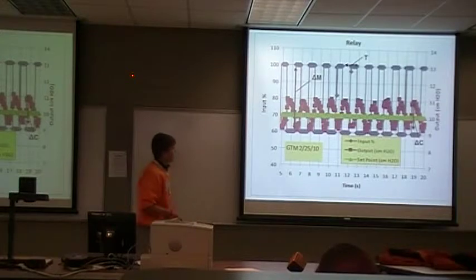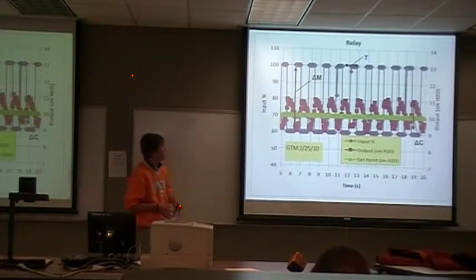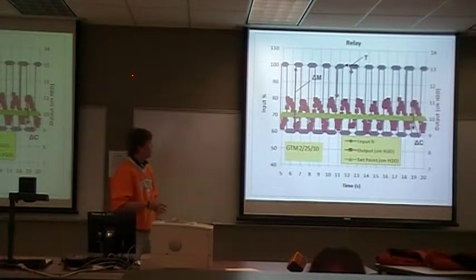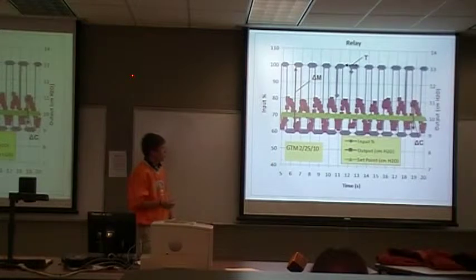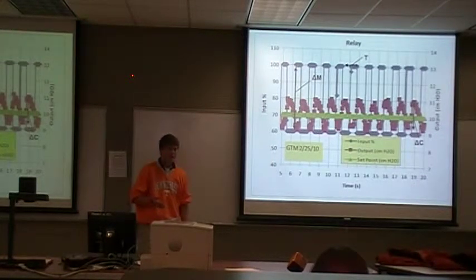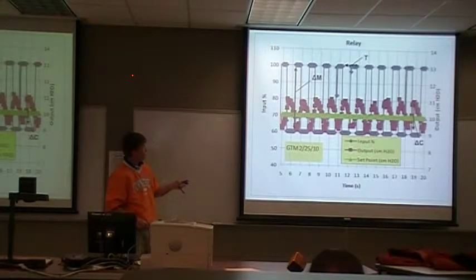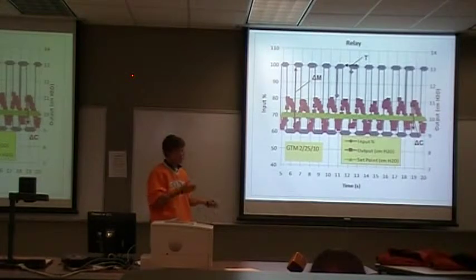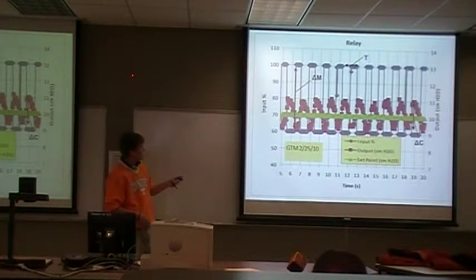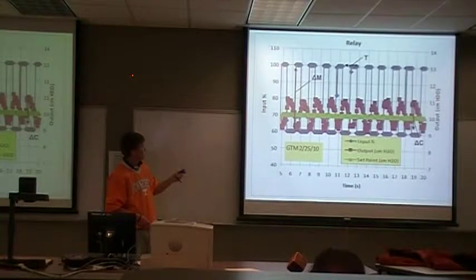For the relay feedback experiment, we set two different input values that we wanted the output to oscillate between. For this case, it was between 60 and 100% input. It would start out at a certain input and give an output. We had a set point — the green line here — and once the output, shown in purple, reached that set point, the input value would jump back down to the other input value. So, for instance, it went up to 100% input, the output reaches the set point, and the moment it does, the input jumps down to 60%, and it begins to cycle.